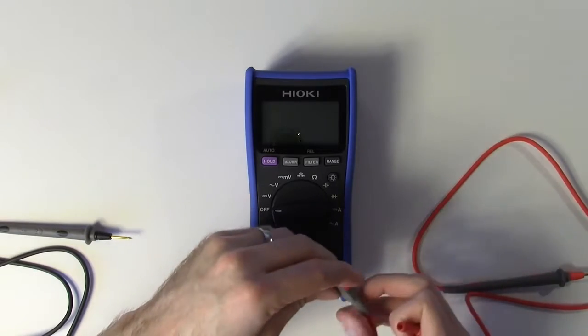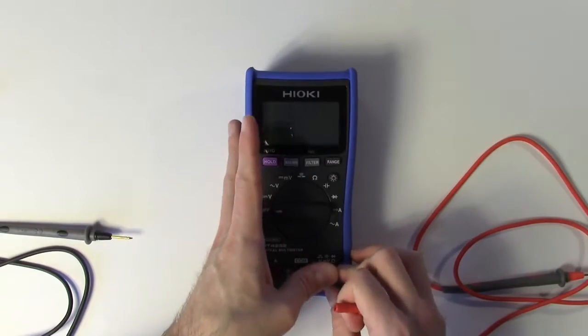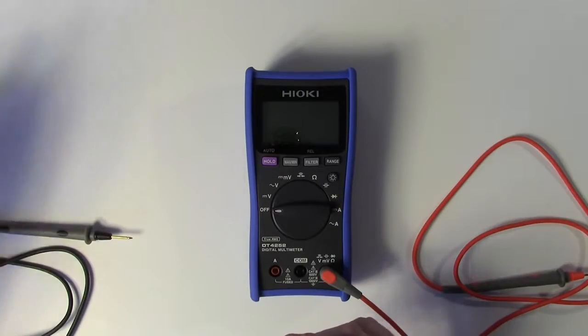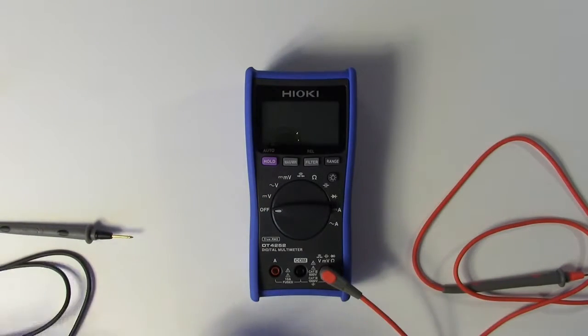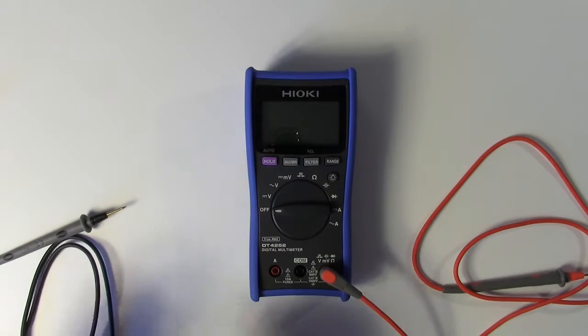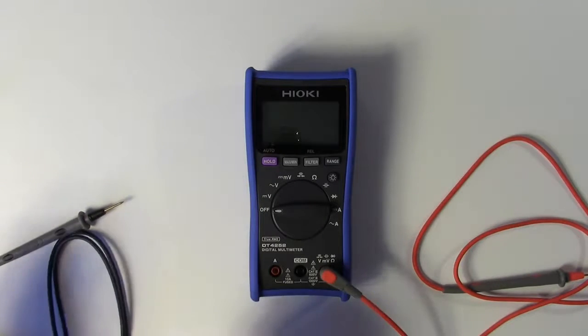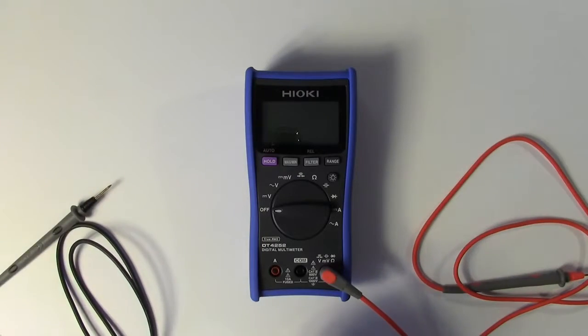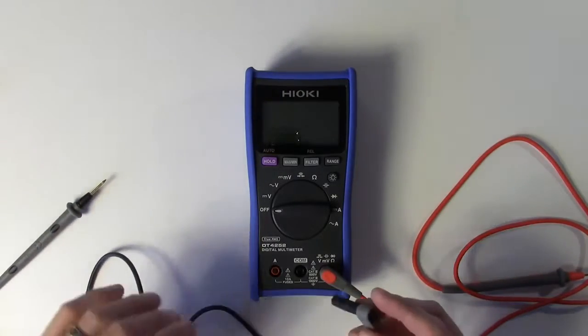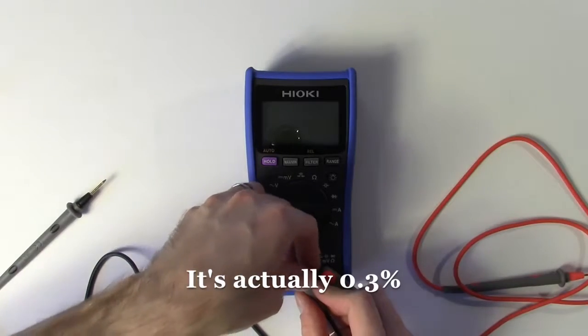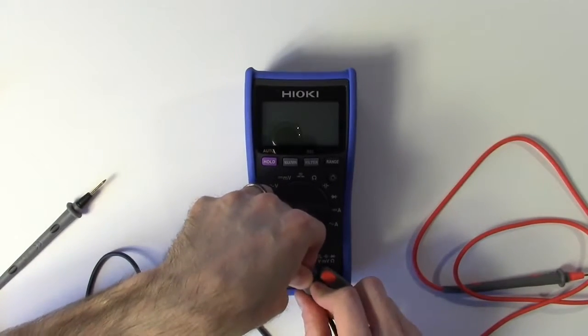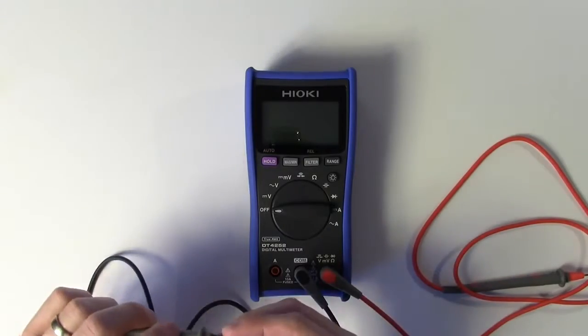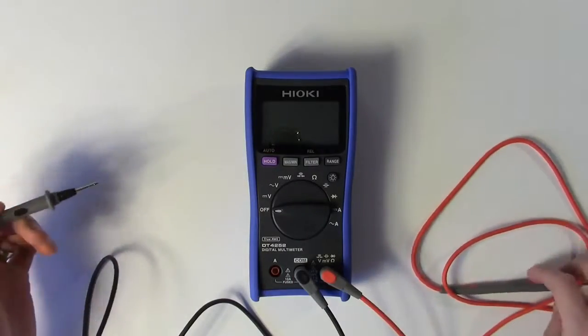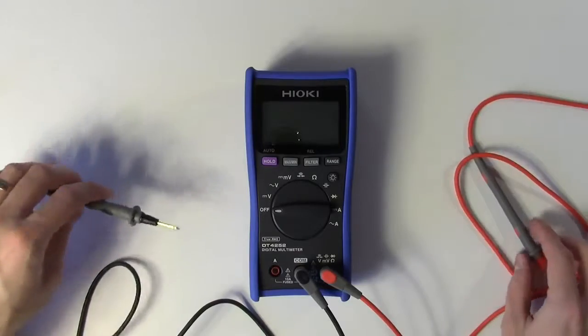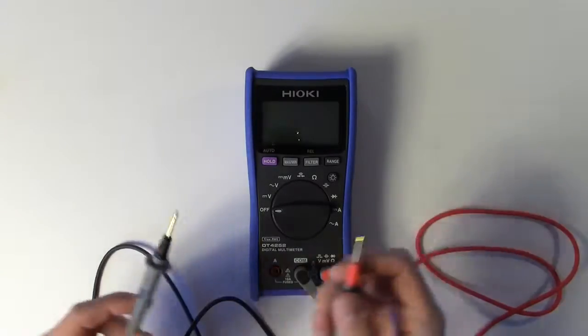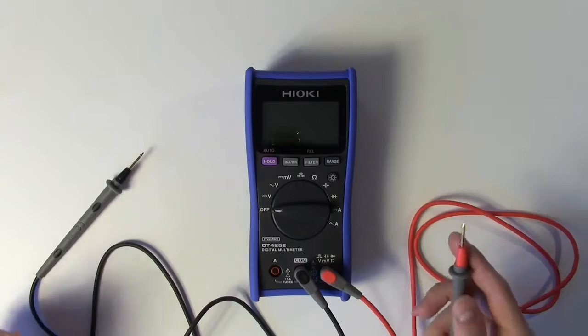I might as well give you some basic specs on this meter while I get set up here. It does have a DC voltage range of anywhere from 600 millivolts to 1000 volts across 5 ranges. On the DC voltage, its accuracy is within 0.5% plus or minus 5 counts. AC voltage, it's 6 to 1000 volts over 4 ranges. This unit does include a low pass filter, so you can cut out kind of the higher end harmonics.